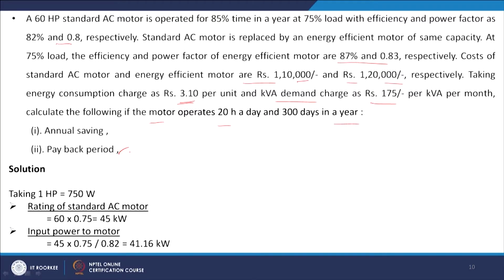This is the time at which the total investment will be returned in terms of expenditure of money. There may be two cases: one is the total amount which you are investing, or another is the gap between the standard and efficient motor. So, now the problem statement: 60 HP is given. 1 horsepower equal to 750 watt we know, if we can assume, then 60 horsepower is 45 kilowatt. So, this is the rating of the standard AC motor, and then the input power to the motor, that will be 45, it is with 75% load.